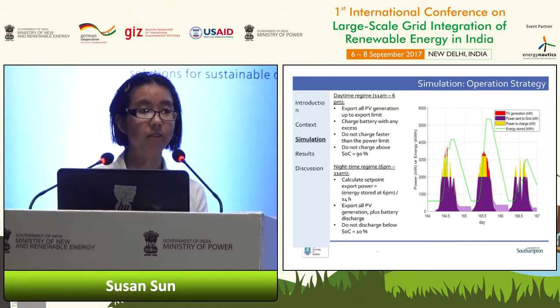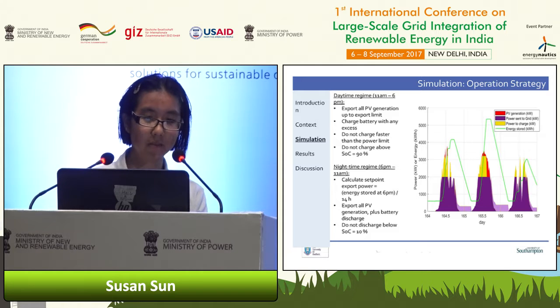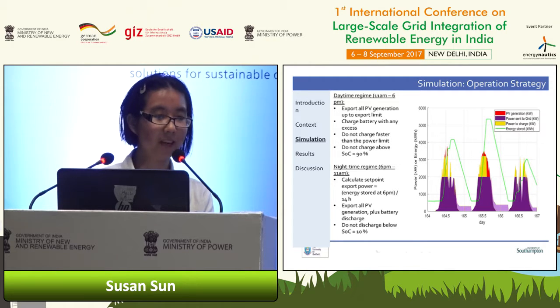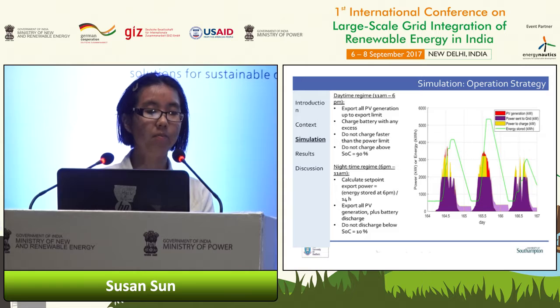So the operating regime has 2 regimes. During the day, all PV generated is exported up to the 2 megawatt limit, and then any excess is used to charge up the battery up to a power limit, which we set in the power converter, and no charge is allowed above 90% state of charge. You can see on day 165, both the power limit and the energy limit kick in soon after each other around midday, and you can see the curtailment in red there.